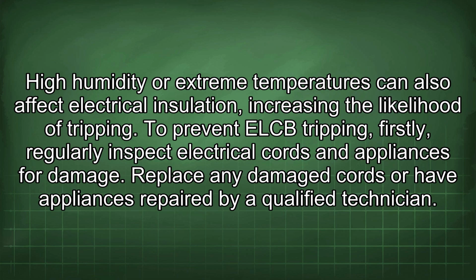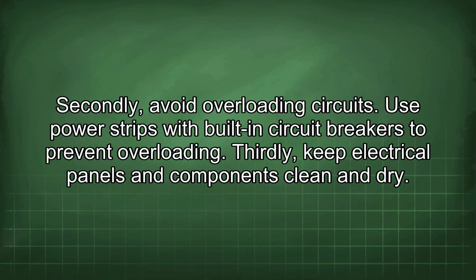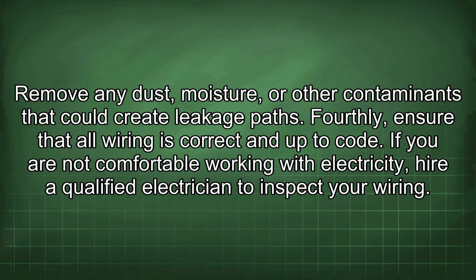To prevent ELCB tripping, firstly, regularly inspect electrical cords and appliances for damage. Replace any damaged cords or have appliances repaired by a qualified technician. Secondly, avoid overloading circuits. Use power strips with built-in circuit breakers to prevent overloading. Thirdly, keep electrical panels and components clean and dry. Remove any dust, moisture, or other contaminants that could create leakage paths.